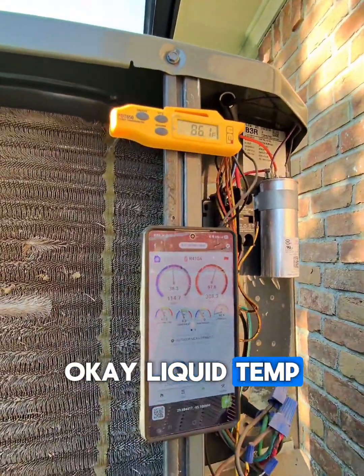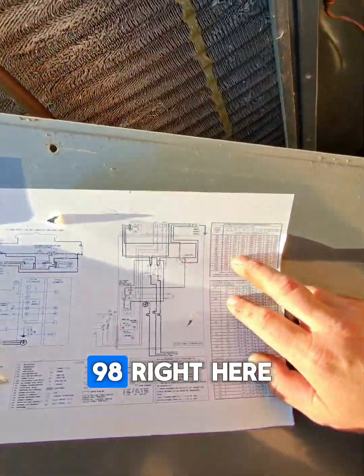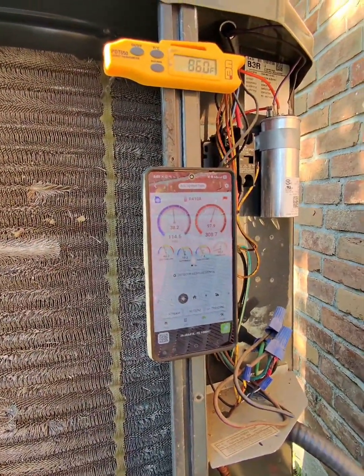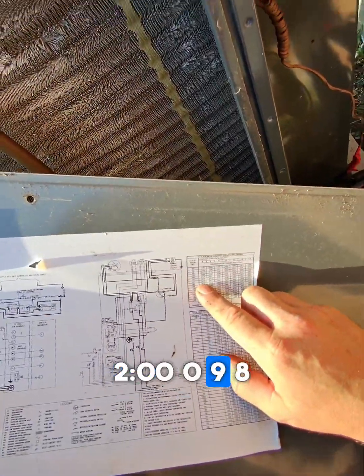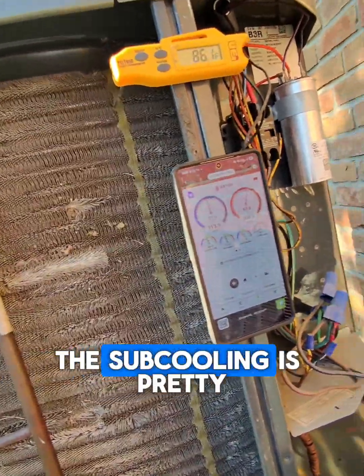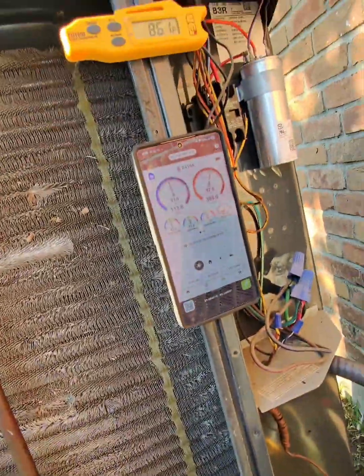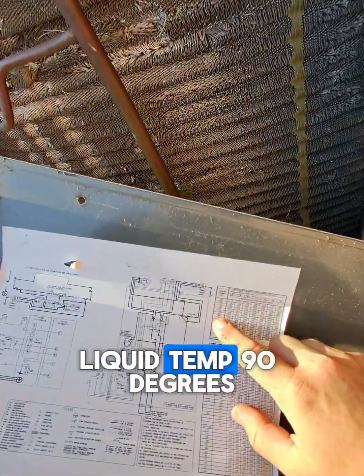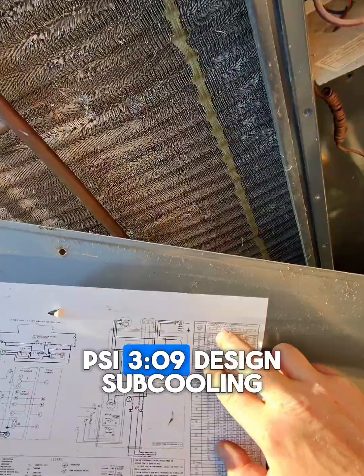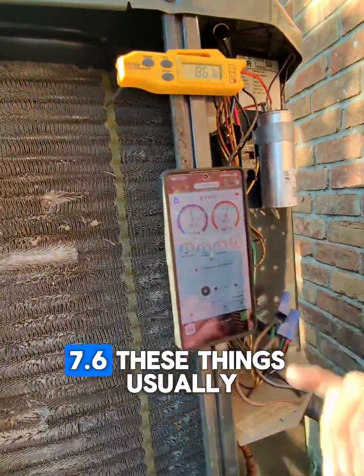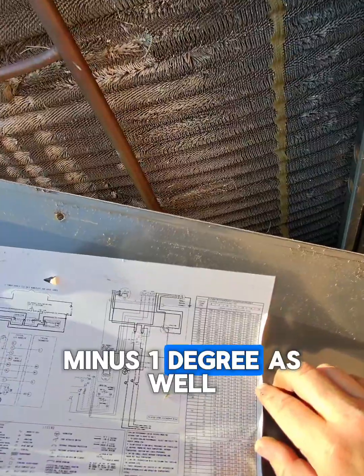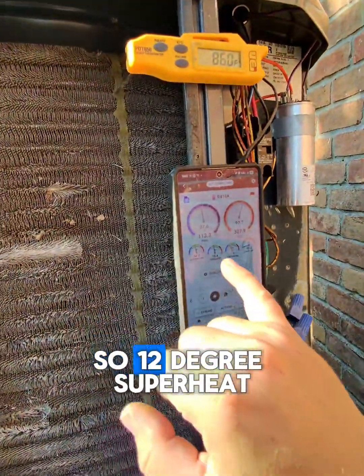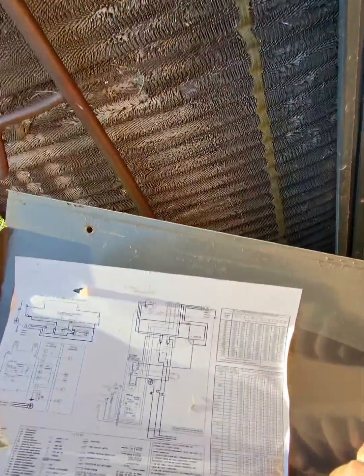Okay, liquid temp, 98, 308, 90 degrees, 209, 8. The subcooling is pretty much on par. We've got 90 degrees on our liquid line, liquid temp, 90 degrees. About 308 on our PSI, 309. Design subcooling about 8 degrees, 7.6. These things usually have a plus or minus 1 degree as well. So 12 degrees superheat, 7.6 subcool. Pretty much on point.